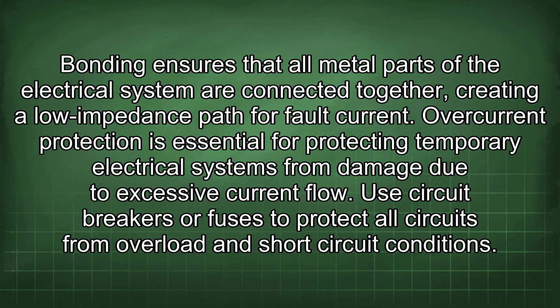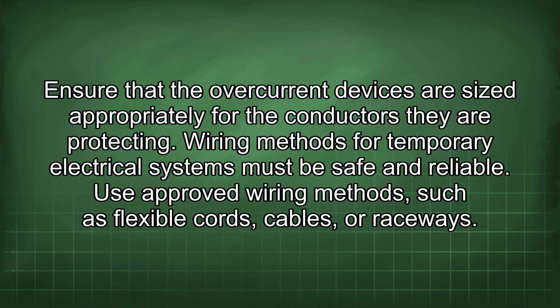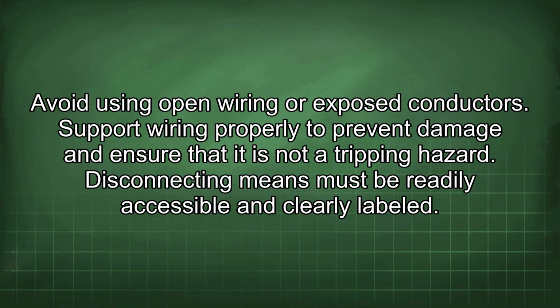Overcurrent protection is essential for protecting temporary electrical systems from damage due to excessive current flow. Use circuit breakers or fuses to protect all circuits from overload and short-circuit conditions. Ensure that the overcurrent devices are sized appropriately for the conductors they are protecting. Wiring methods for temporary electrical systems must be safe and reliable. Use approved wiring methods such as flexible cords, cables, or raceways. Avoid using open wiring or exposed conductors. Support wiring properly to prevent damage and ensure that it is not a tripping hazard.